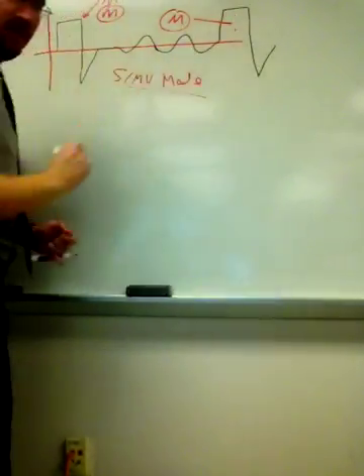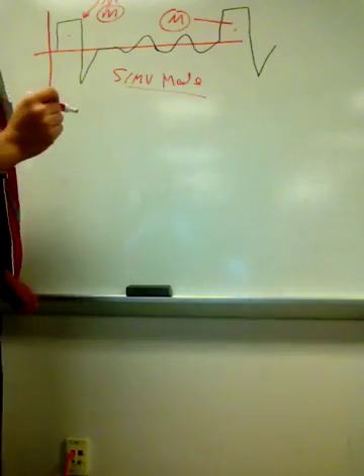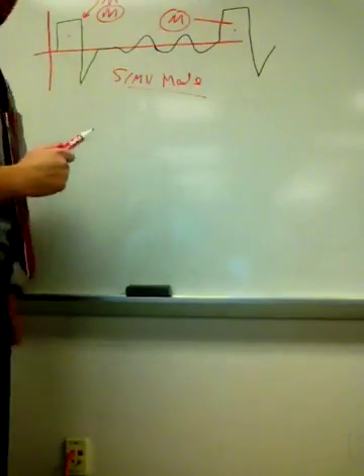Because I have a mandatory breath here, everyone would agree, and a mandatory breath here. So mandatory, mandatory, and of course we can tell that this is a volume control mode. The mode obviously is SIMV, but the type of ventilation, the cycling mechanism is volume control.